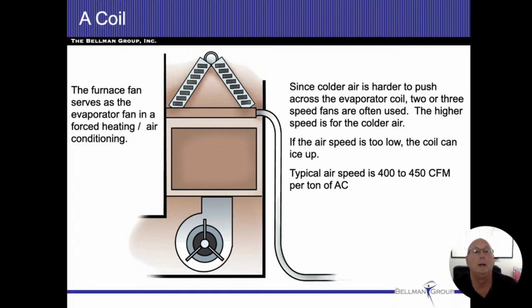All right. The furnace serves as the fan. So the outside condensing cabinet, where it converts from a gas to a liquid, we have a special fan strictly for that cabinet outside. Inside, however, we use the same circulation fan that we use to make heat in that house. So that's our blower fan coming across. Colder air is harder to push. That's a true statement on there.